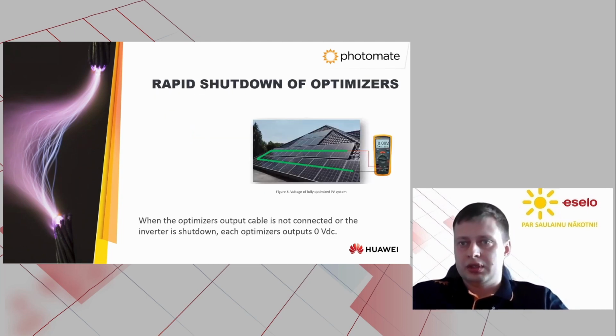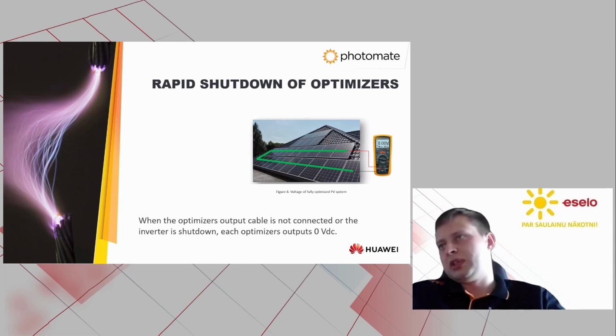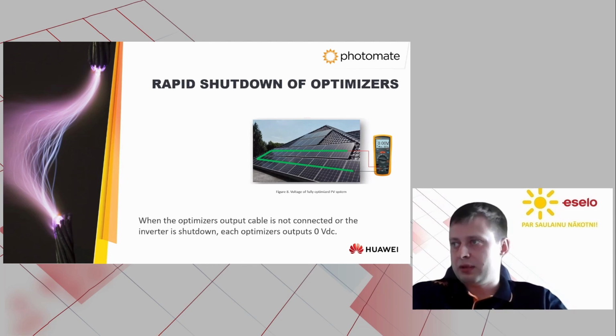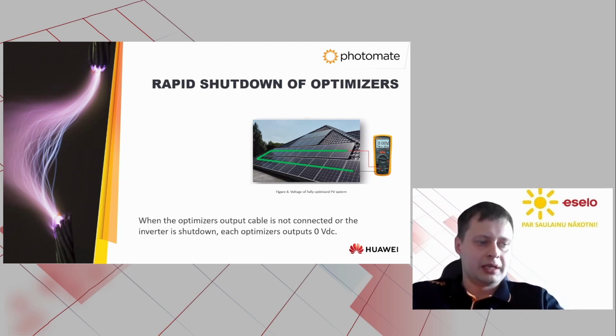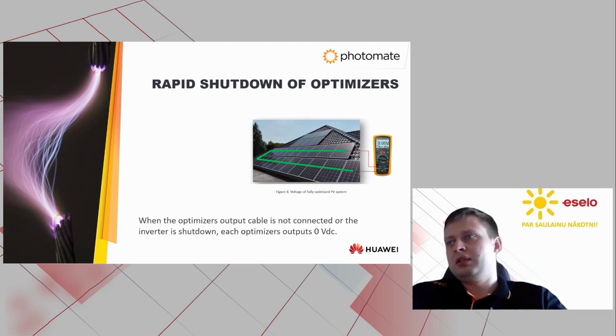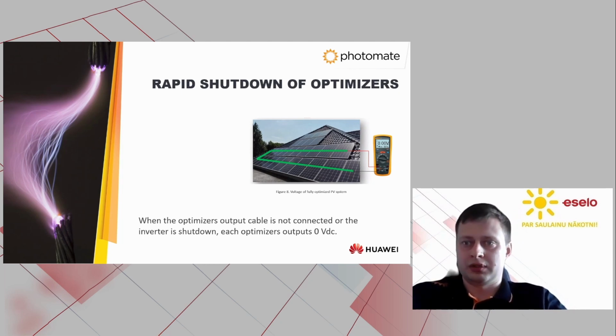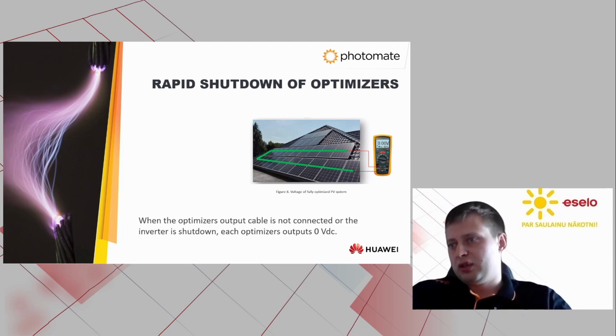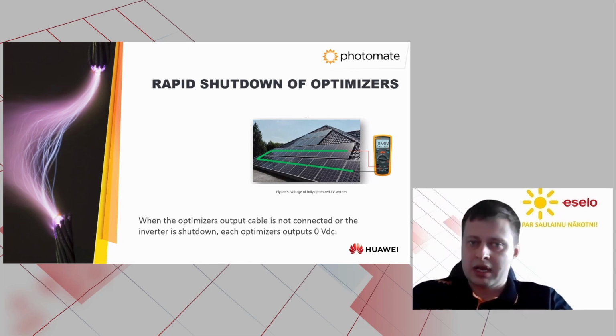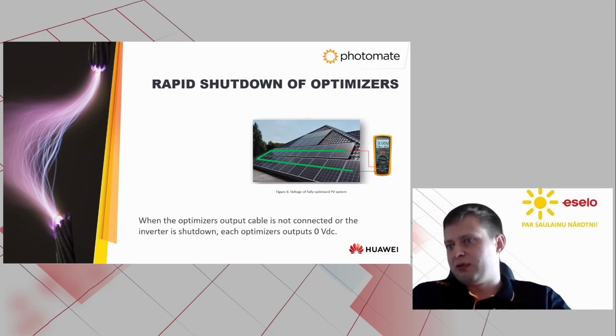Second function, which is worth mentioning, is more related to the residential installation. It is the rapid shutdown function. Rapid shutdown means that if the inverter is disconnected from the optimizers, the optimizer output becomes 0 volts. So in case of fire or if maintenance is needed on the roof, it is a pretty important feature, because instead of 100s of volts, you are getting zero volts, and it will be safer. And in case of fire, it can be much easier for firefighters.